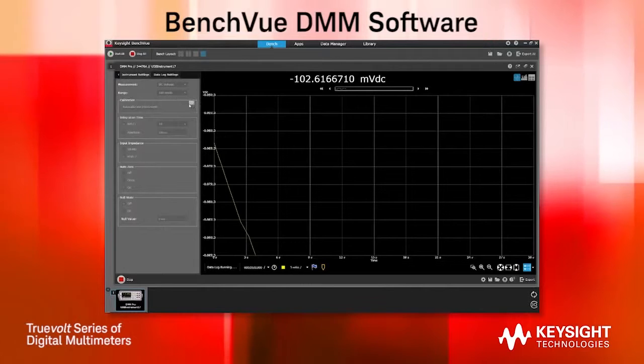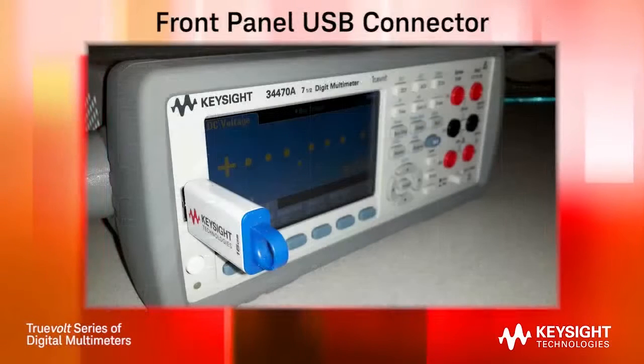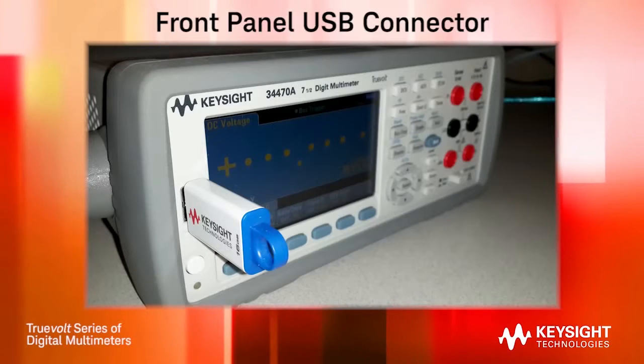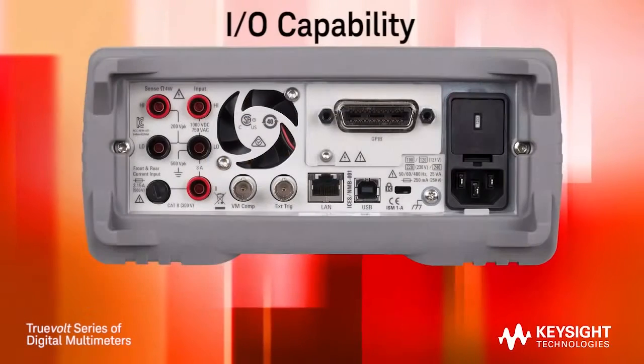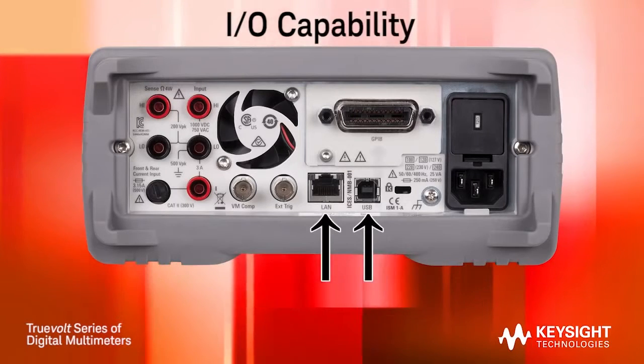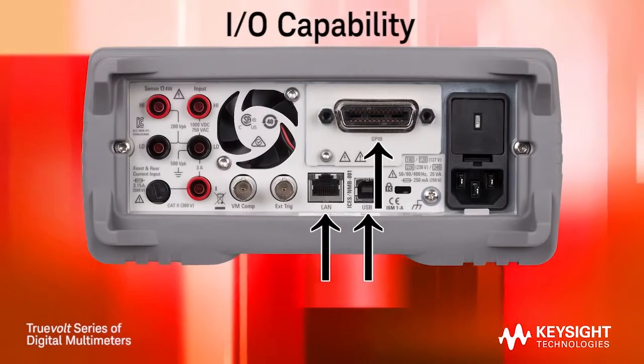You can view your data and connect to other Keysight instruments. The front panel USB memory connector can be used to store data from the DMM or to download files to the DMM. Standard I/O for the 34465A and 34470A is USB and LAN. GPIB is optional on both models.